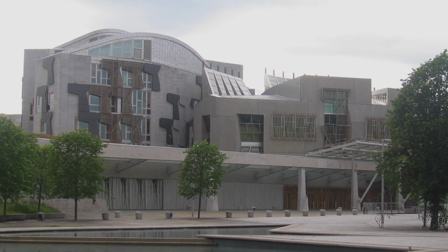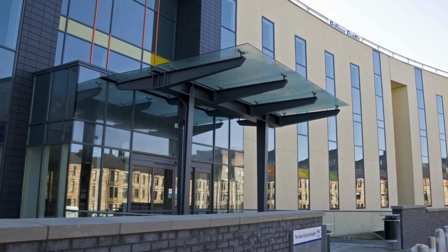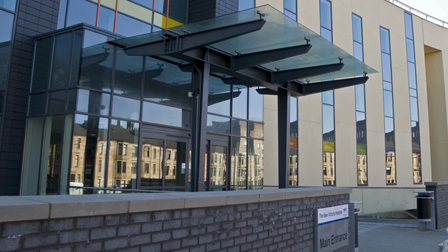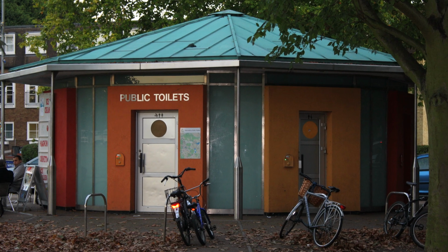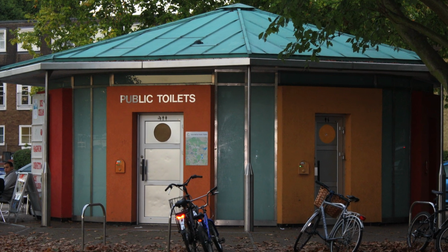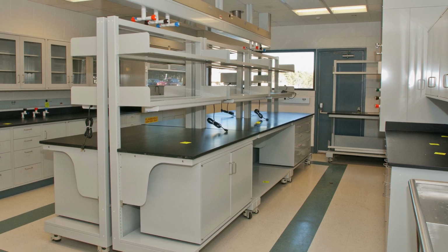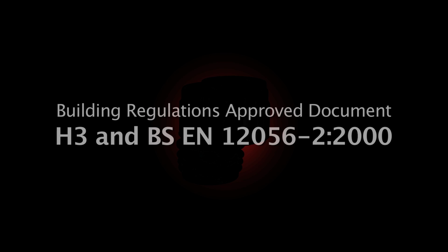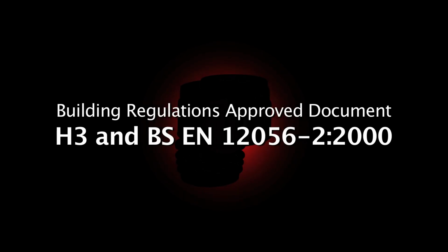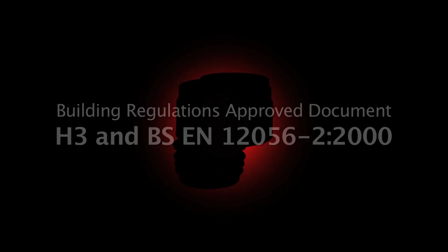A single McAlpine AAV has the capacity to maintain pressure in an intermittent running system, such as a house or office, a frequently running system, such as a hospital, school or hotel, a continuously running system, such as a public toilet, and in special circumstances, such as a laboratory. The use of AAVs is approved under Building Regulations Approved Document H3 in BS EN 12056, though only AAVs manufactured to BS EN 12380 are suitable for use in sanitary pipework systems.